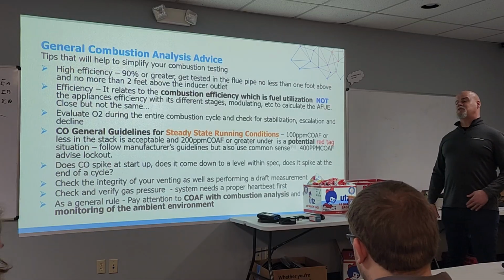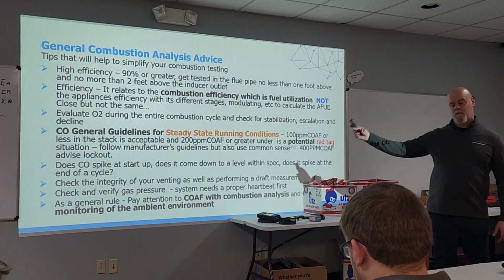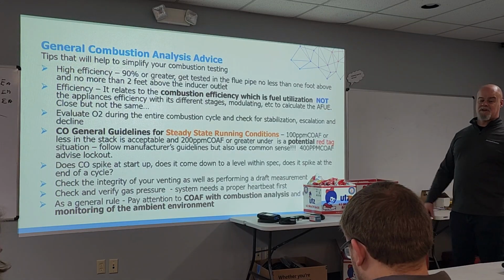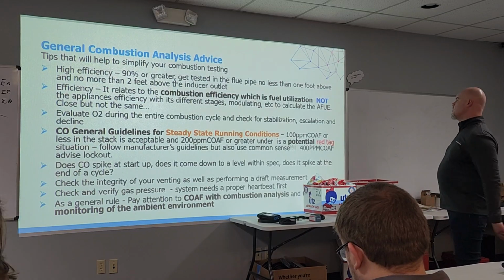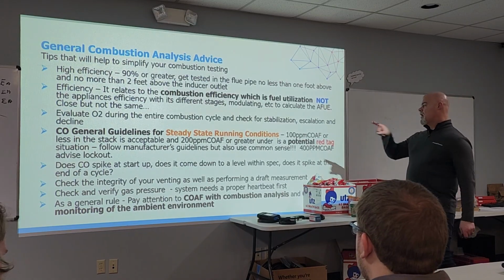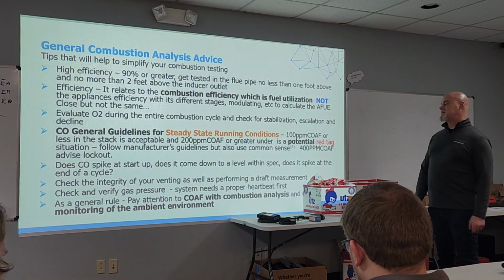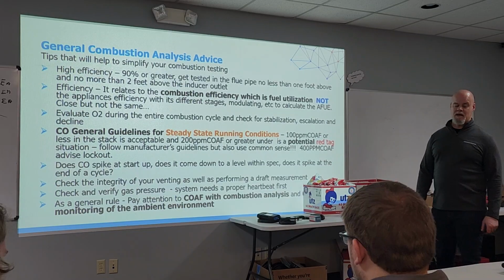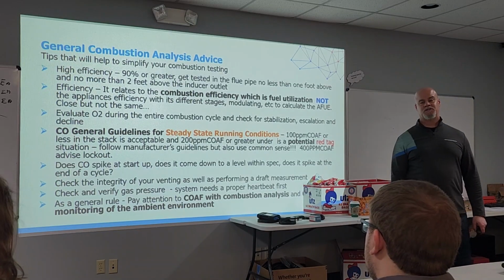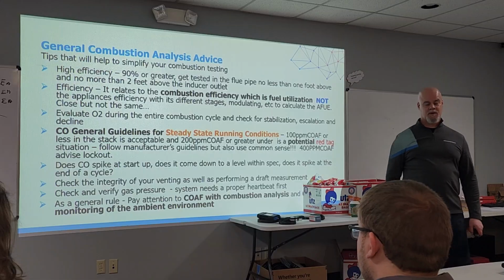That is why we do our jobs correctly. That is why we are professionals, and we use CO air free, which is on our analyzers and on the other competitors' too. That's why we use CO air free for our combustion testing. 200 ppm or greater at steady state is considered a potential red tag situation, which means just slow down.